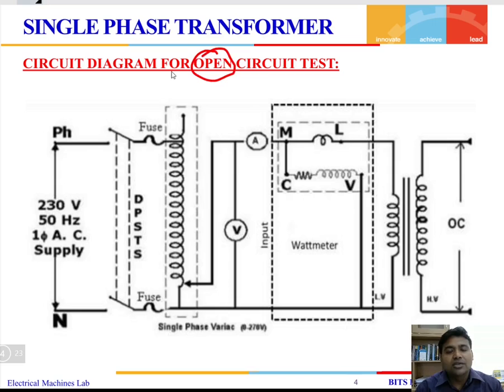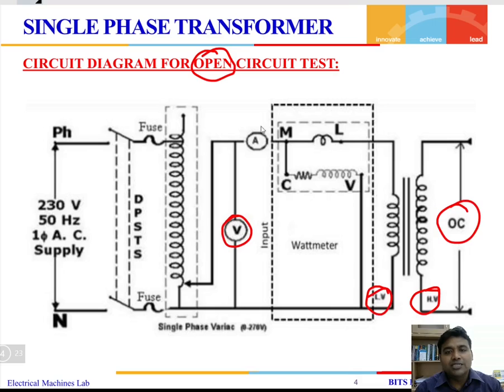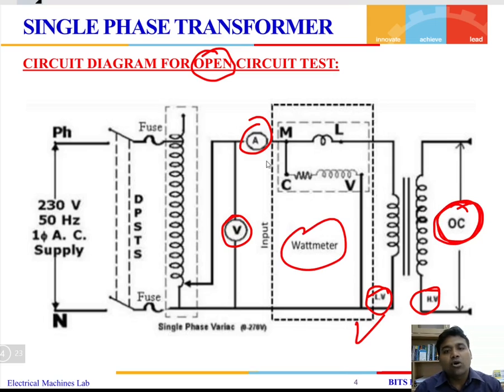Let us see the circuit connection for the open circuit condition. We generally keep the high voltage side open and all the measuring instruments are connected on the low voltage side. The voltmeter, ammeter, and wattmeter are connected on the low voltage side, and the high voltage side is kept at open circuit. So all measurements are done on the low voltage side.